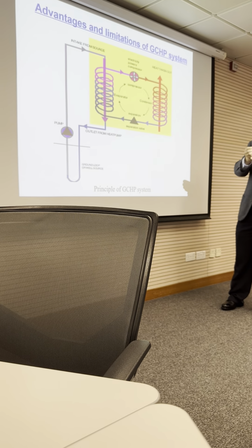So one problem appears. If we use such a system throughout the year, like PolyU, we have chilled water supply nowadays. Throughout the year, what happens? We have to reject energy continuously to the ground. Then heat accumulates underground, and the temperature is higher and higher, then the COP is lower and lower. We have compared the performance with the traditional air-cooled system, and it's not economical. So that's why in Hong Kong, not in Guangdong area, not many such systems are used. Only some trial projects. So in hot weather areas, it's not popular. The payback is very long.